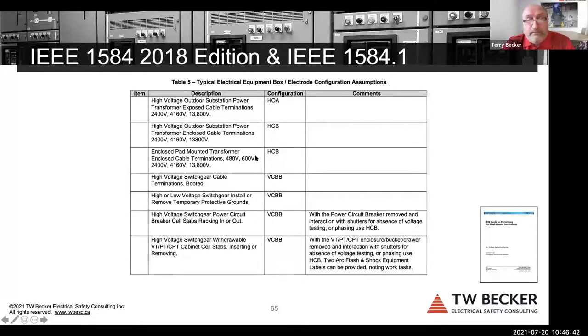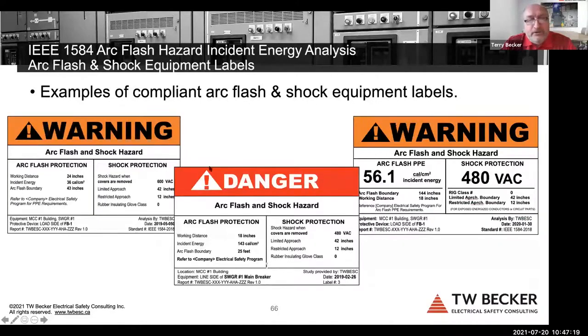And I have a table where I make recommendations. And ultimately, this should be part of an employer's electrical safety program, that the technical specification is linked to it, because these studies, they provide the hazard information, and the information is put on a label, right? So really, the label should be controlled by the electrical safety program. And again, the owner of the electrical equipment should have a technical spec to control the consultant, but the consultant should also work with the client if there's no spec to educate them, but don't be too conservative, right? You need to be realistic in interpreting 1584. And again, the labels that I mentioned earlier, right?